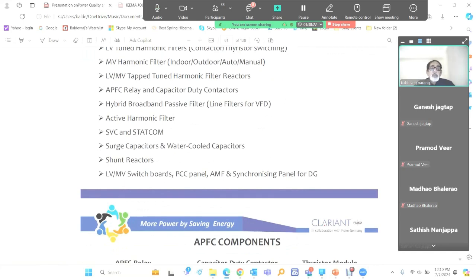Shunt reactors also are required these days at many places because we have long transmission lines, and when there is no load, the power factor goes to the highly leading side and there is a very heavy penalty. So this we correct by putting shunt reactors.